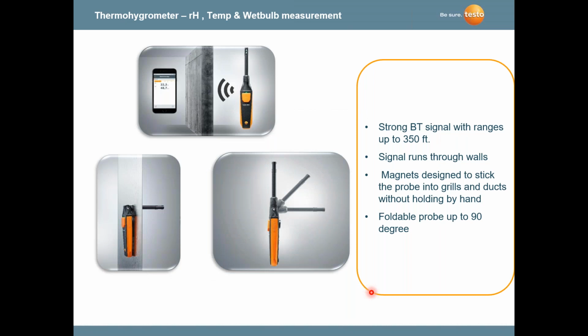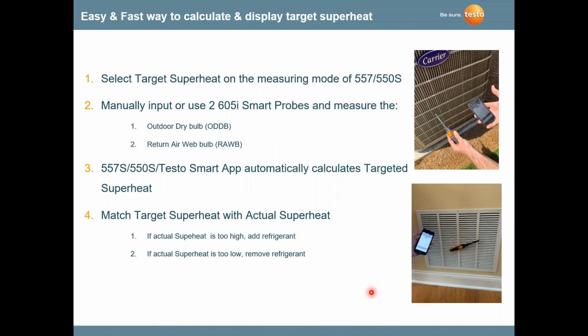Today, again, we're using digital instruments that measure relative humidity, temperature, and wet bulb readings, and they can be located on your system, or you can store the readings in your app. But let's say you got a return air wet bulb reading inside the home. You've got one outside near your condensing unit to get your outdoor dry bulb, and the instrument automatically would calculate your targeted superheat. This is when you're using your fixed metering devices, your capillary and your piston.